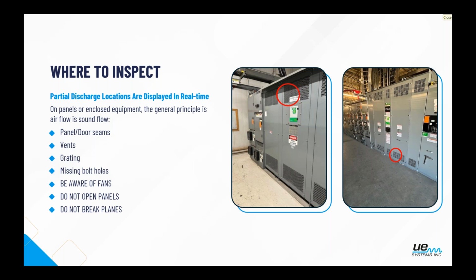So typically panels around the seam of doors, the panel itself. In these two pictures, venting, any sort of air exchange, grates. If there are missing bolts, so now we have an open hole, that in itself is an ultrasound inspection port. The biggest thing to be aware of is: is there a fan running inside this piece of equipment or around you? And of course, we're absolutely not opening panels to make an ultrasound inspection, especially if you do hear an event happening inside of it. And if you are inspecting from an opening, we're not breaking the plane.